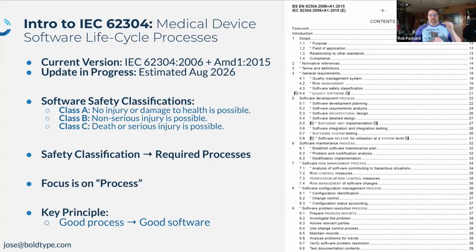You have these 5.1 through 5.8 requirements of 62304. That tells you how you develop software and how you document it. There are shalls, and the FDA requires that you say you actually follow that. Then on the other side, for the documentation, they're asking you for the end result: please attach it. We'll touch on how those two end up mapping.